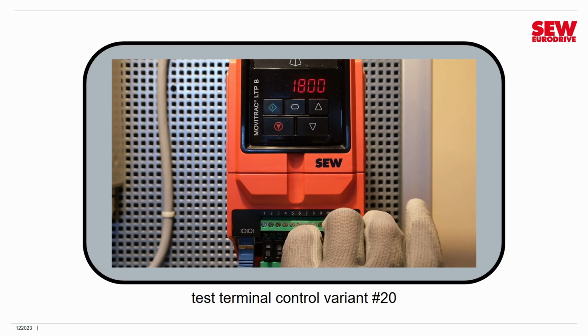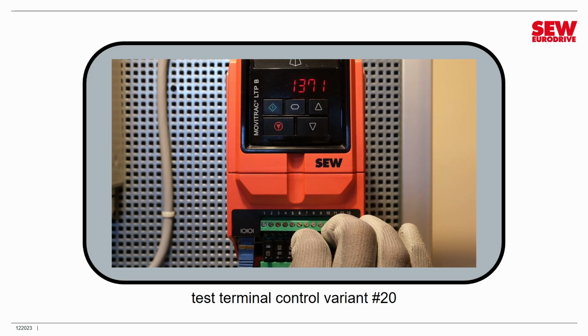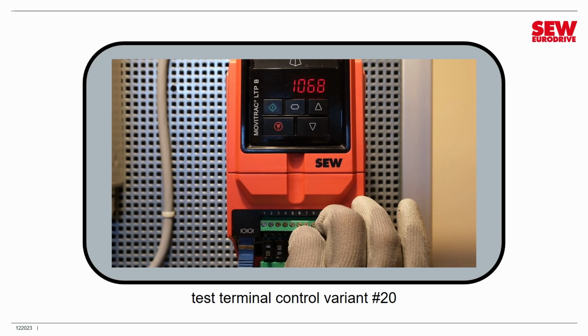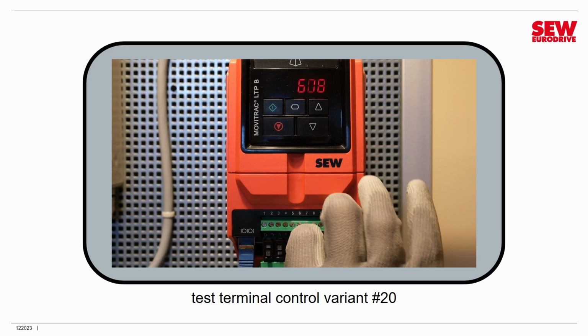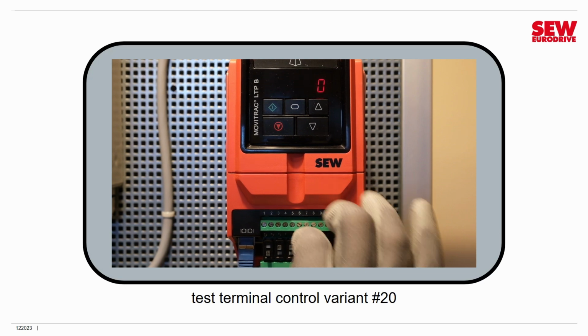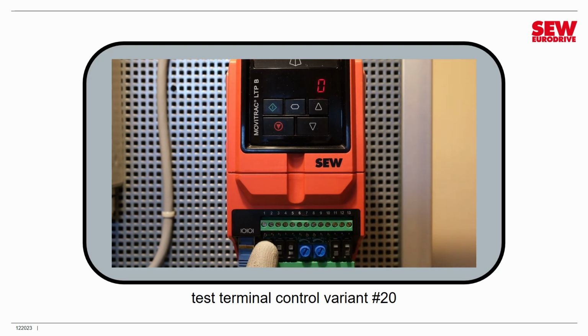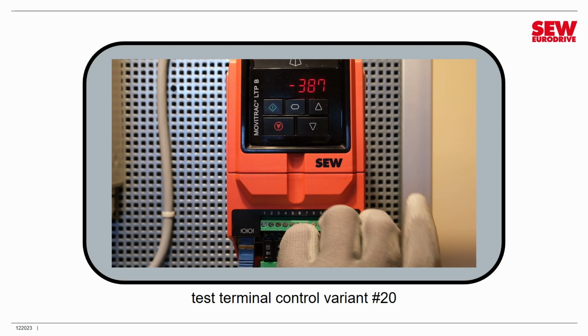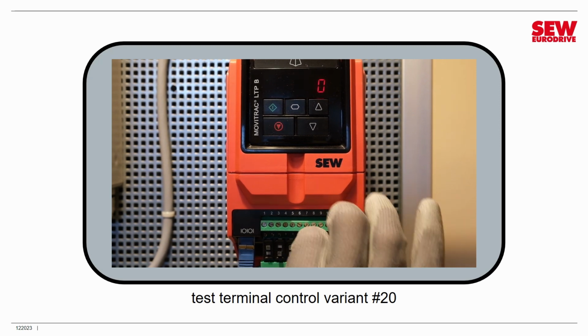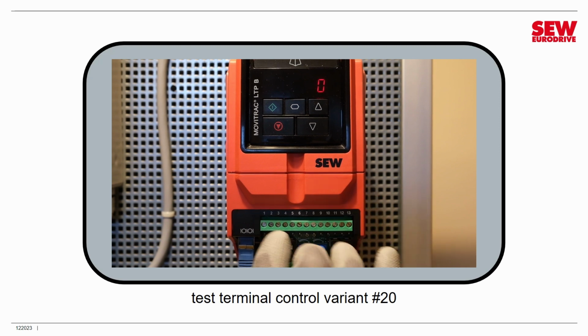I'm going to rotate the potentiometer on digital input 4, and I'm going to flick it back and forth, so it's kind of going on and off, and you can see we're decelerating, so the digital potentiometer there is going down. All right. Now let's disable that and go counterclockwise by turning digital input 2 on. We'll do the same thing. We'll pulse our imaginary push buttons here, and we'll ramp our speeds up and down. So you can see that works pretty well. It would work better with push buttons, of course.